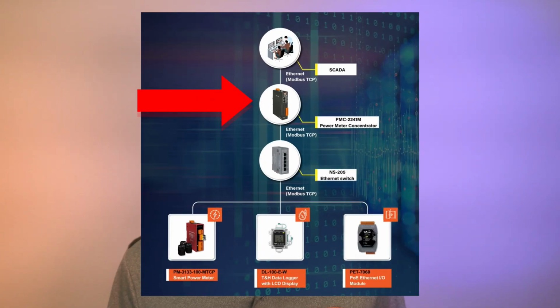All of that data is then sent to a PMC-224IM power meter concentrator. This concentrator collects and stores the readings, runs if-then-else logic to trigger events, and forwards alerts to the control center. With dual Ethernet ports, it keeps the power network separate from the corporate network, a key design choice for both security and bandwidth management. By combining environmental, access, and electrical data in one place, the team gained full situational awareness.